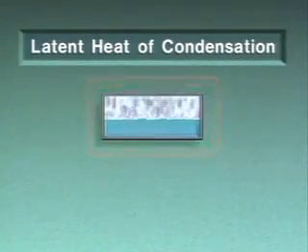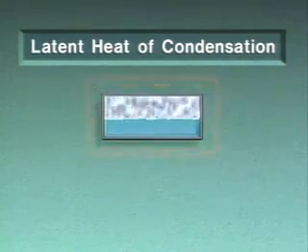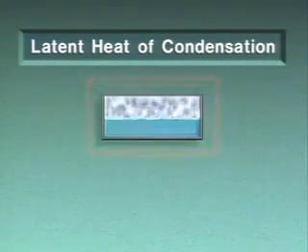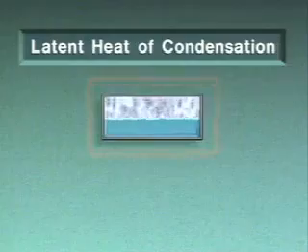The heat that must be removed or rejected to completely change a vapor to a liquid at a certain temperature and pressure is referred to as the latent heat of condensation. When the refrigerant in a refrigeration system receives heat from the substance that is being cooled, it receives the latent heat of vaporization and becomes a vapor. When the refrigerant rejects heat, it gives up the latent heat of condensation and becomes a liquid.